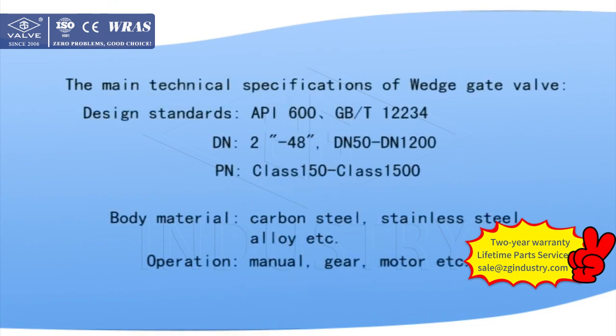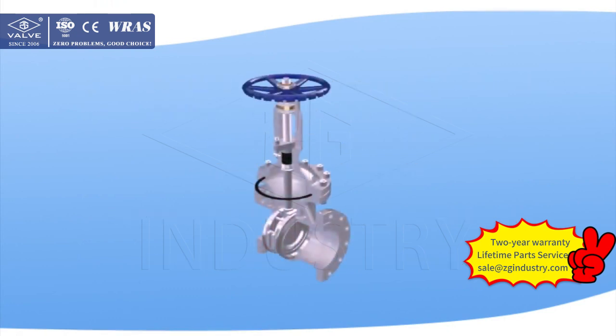The main technical specification of wedge gate valve. Design standards: API 600, GB/T 12234. Size: 2 inches to 48 inches, DN 50 to DN 1200. Pressure class: Class 150 to Class 1500. Body material: carbon steel, stainless steel, alloy, etc. Operation: manual, gear, motor, etc. Product fabrication is strictly according to API 600.